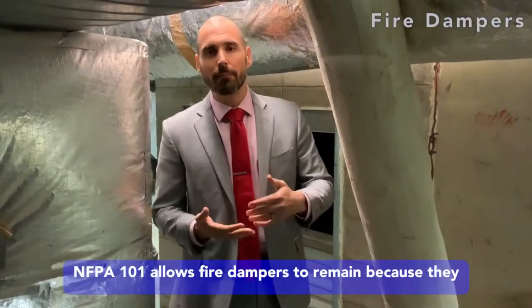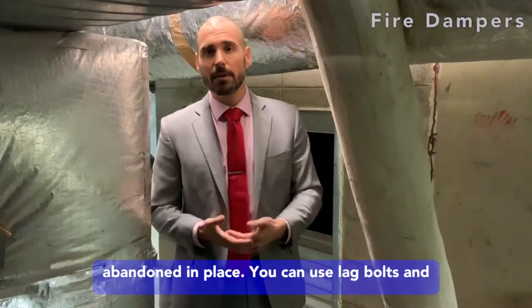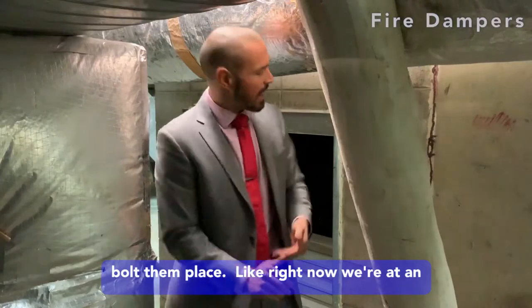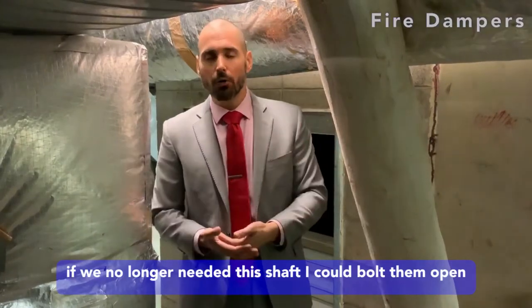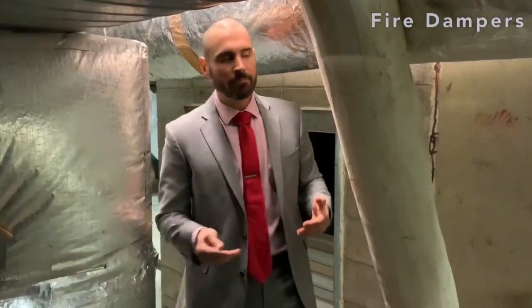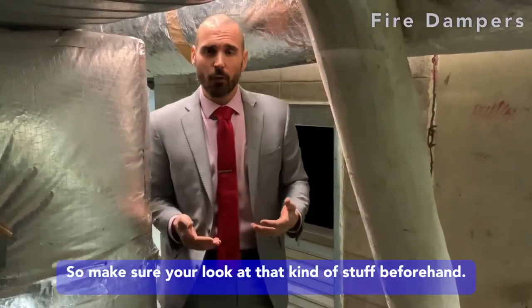NFPA 101 allows fire dampers — because they are not obvious to the public — to be abandoned in place. You can use lag bolts and bolt them in place. Right now we're at an air transfer grill on the shaft, so if we no longer need the shaft, I can bolt them open, keep them closed, whatever the requirement ends up being. Make sure you look at that kind of stuff.